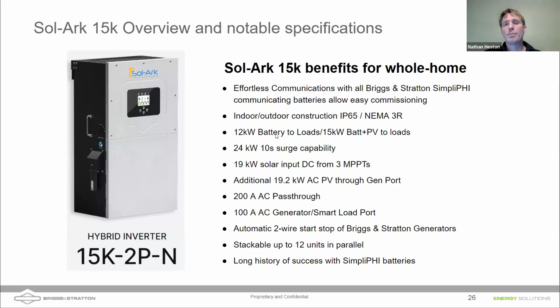It does 12 kilowatts of battery to loads. As I mentioned earlier, if you have solar available, it will do 15 kilowatts continuously to loads. It does, however, have the ability to surge. It can surge for 10 seconds. I think I said 5 earlier, but it's 10 seconds at 24 kilowatts. So if you're starting a heavy load, you can get that surge. I will point out that this transformerless inverter is split, right? So if you go over 6 kilowatts per leg, you can have issues with imbalance. But with that 12 kilowatts, typically large loads are 240 volts, so for the most part, you have the ability to start those large loads with this surge.